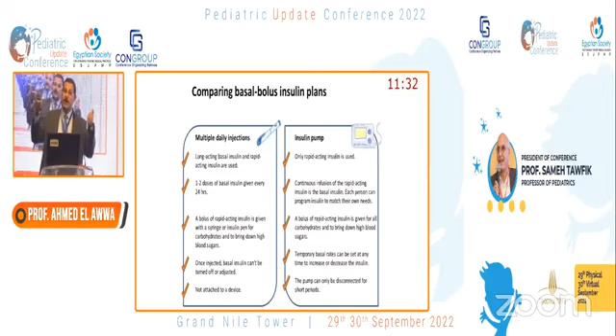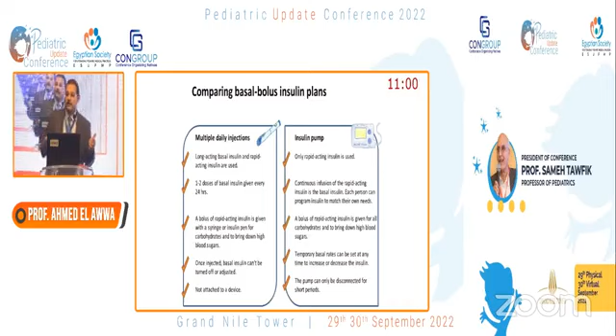I can change the percentage of the dose delivered as basal insulin, while the precise dose of insulin can be as low as 0.025 units by the pump, which is one-tenth of a quarter of a unit, while the least dose I can deliver through the MDI is 0.5 units only. While with the pump, the child will have an attached device, while with the MDI, there is no attached device.